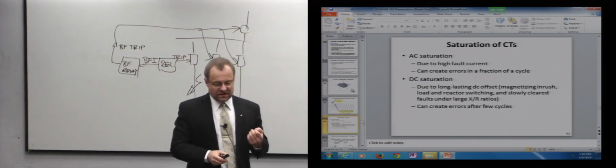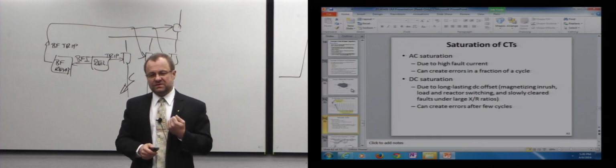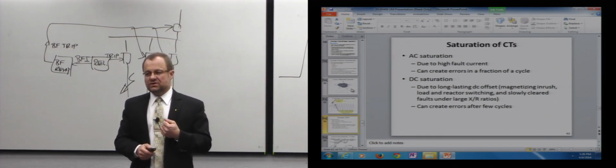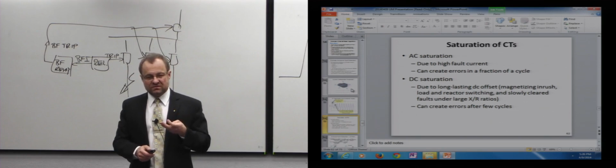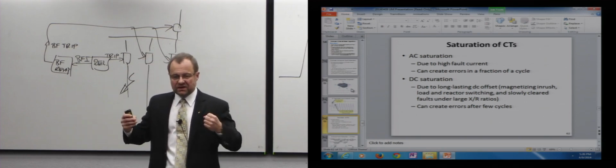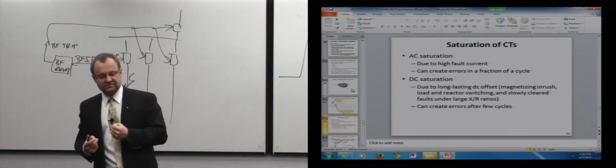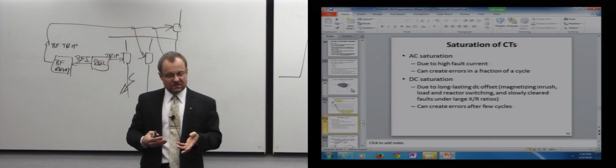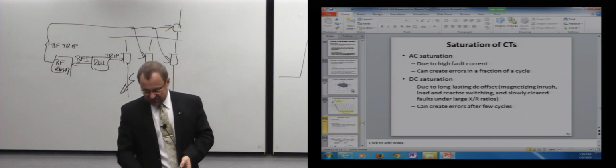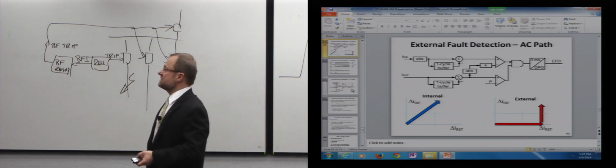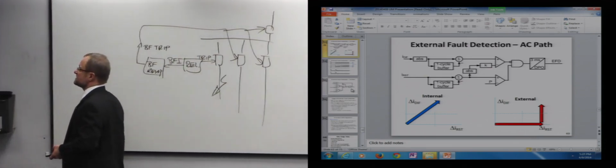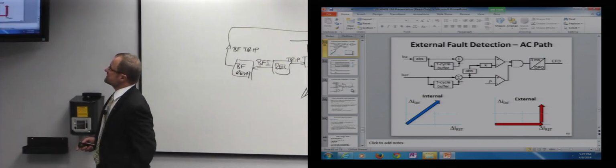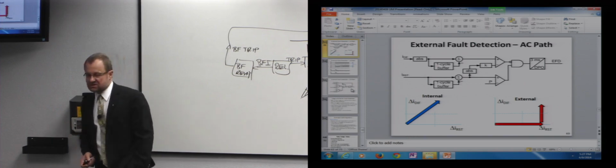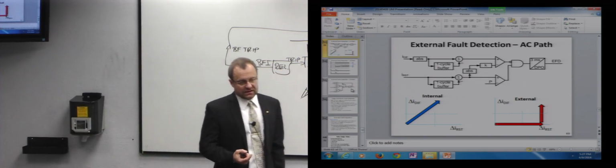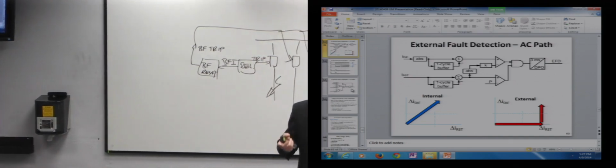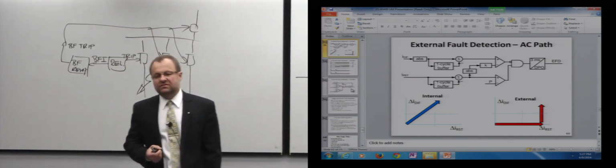So this is a more dangerous type of saturation because it happens when the current is low. Normally what we do for CT saturation is we use the percentage restraint, meaning that if the currents are everywhere big, we increase the threshold, right? When the currents are low, the threshold is low, so if you have any error, it will come and bite you. So this is another heuristic algorithm that detects CT saturation. What happens here is that we monitor the change in the differential and restraining current. What is the restraining current? It's basically a sum of all the currents around it.